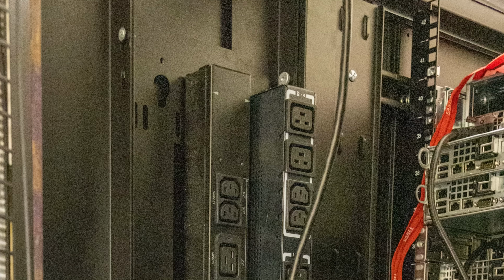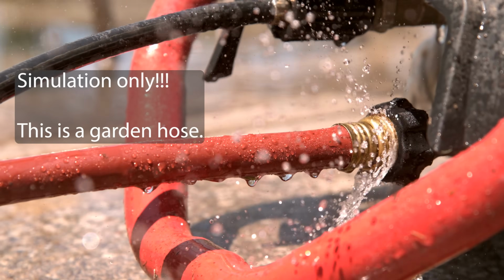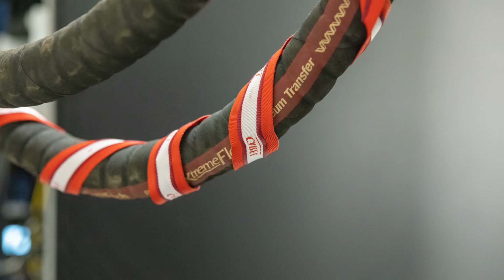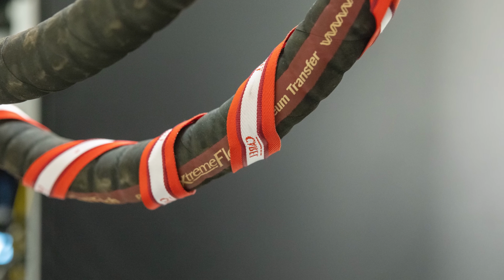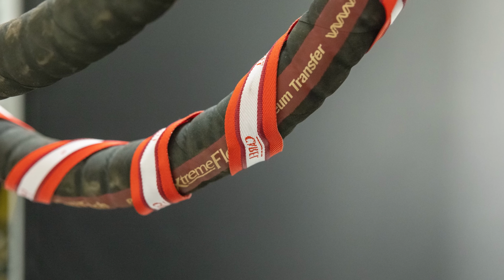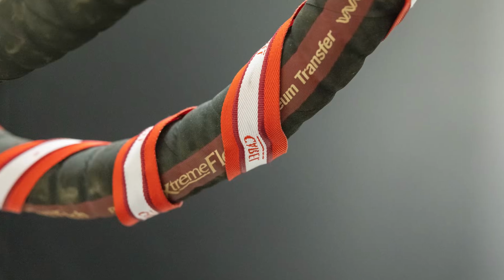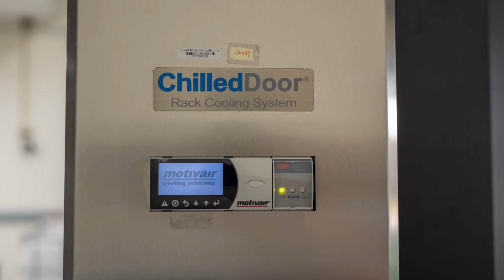And just a quick tidbit, something I thought was pretty interesting: I saw a liquid or moisture detection sensor that you wrap around the fittings, because that's normally where you would see a leak, but also potentially the tubes and the pipes. That is used so that if you do get some kind of leak, you'll have a detection and you can automatically shut down the server and make sure that you don't have something bad happen. I know a lot of folks are going to be really concerned about leaks, but not only is there a whole monitoring solution on these rear door heat exchangers, there's also a solution that is looking for moisture and trying to prevent a catastrophic failure. It was just something that I thought was interesting and I wanted to show you.